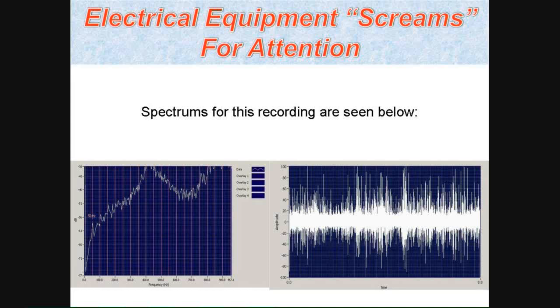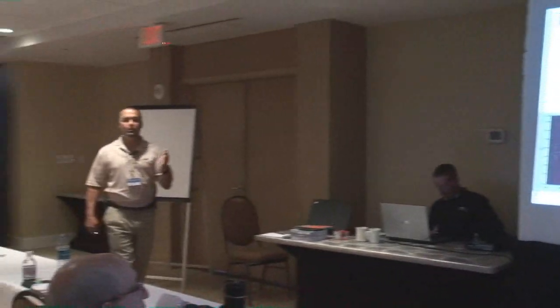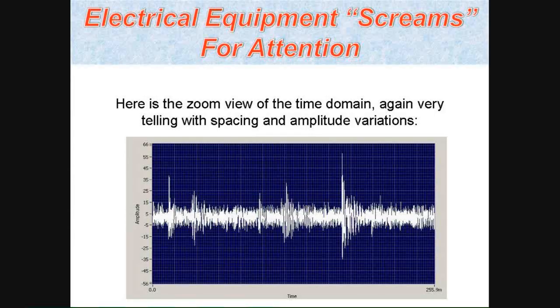And when we analyze this, what's the FFT show us? Nothing. Not in this case. It's very wanton. But the time domain, once again, has that signature or footprint that we're on the lookout for. We have the excursions. We have variations in the amplitude or the intensity of the discharges. And there's not a pattern to the spacing in between these, or the timing, if you will. And I think in the paper it goes into a little more detail on how that relates to an electrical sine wave. When you zoom in on that tool, just take a slice in time on there, it becomes even more clear how nonlinear these excursions and timing are on the events taking place.